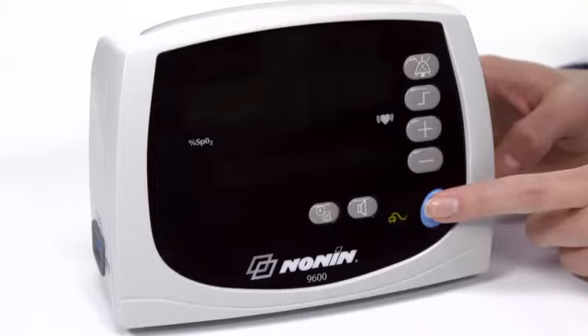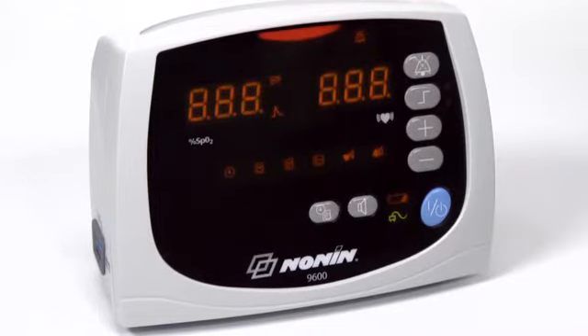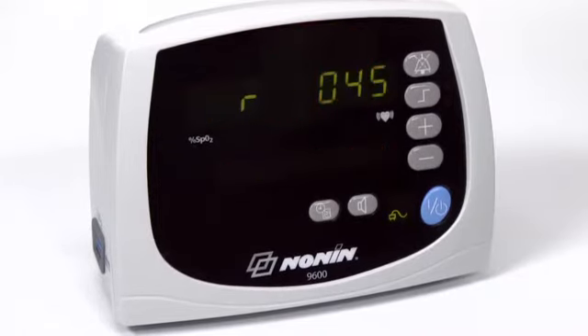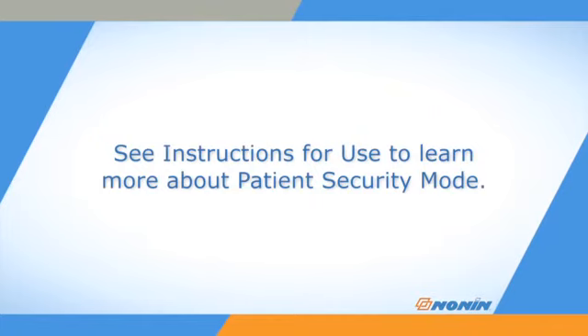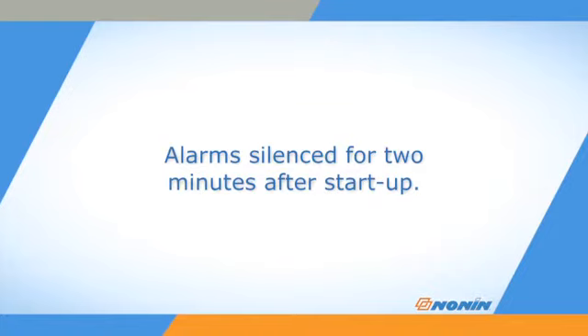A patient security mode prevents changes to alarm limits and a number of alarm and functional settings. During startup, you will see the software revision, PS_DFL, meaning patient security mode is enabled, followed by the upper and lower alarm limits. Refer to the instructions for use to learn how to set or cancel patient security mode or reprogram settings. The alarms are silenced for the first 2 minutes after starting the unit to allow time for adjusting settings and connecting the sensor to the unit.